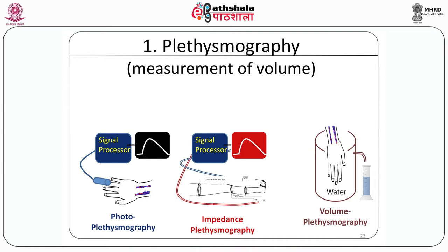Plethysmography means measuring the volume. The three techniques shown are versatile techniques currently used to measure blood flow. The photoplethysmography technique actually indicates blood flow, although it is commonly used for oxygen saturation in critical care monitoring. By using photoplethysmography combined with computational techniques, volume blood flow can be computed for a given area. The impedance plethysmography technique will be described in detail.